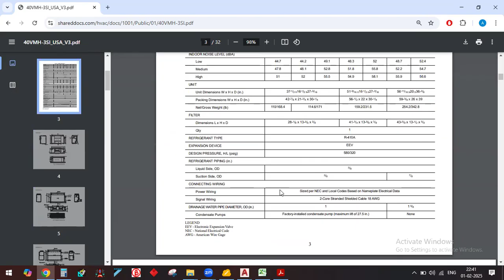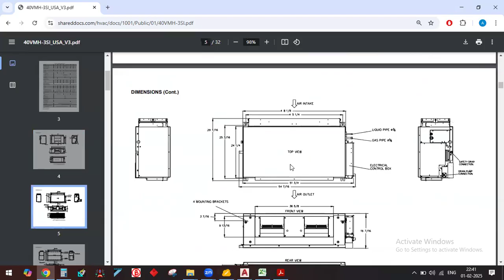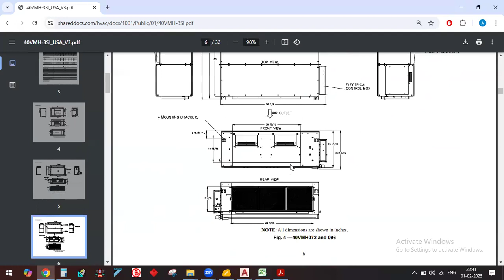See, again, what is given is the dimension of the equipment. But we want the dimension when the equipments are connected in configuration, how the installation is given. So that document we need to search actually. Otherwise, you need to ask the vendor itself. If you are contacting Carrier, you have to specifically ask for these words: installation guide. I want the installation guide for the equipments. Otherwise, you can tell them this is my configuration, 54 HP, 60 HP, so 120 HP is coming. I want, what you can say, the spacing requirements for my units. So they will provide you the guideline.